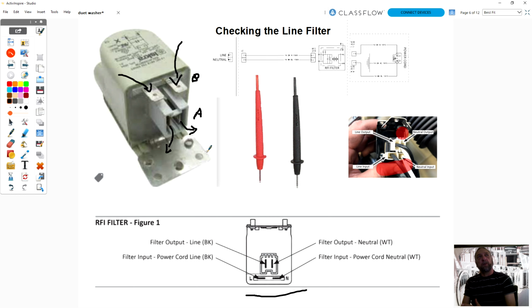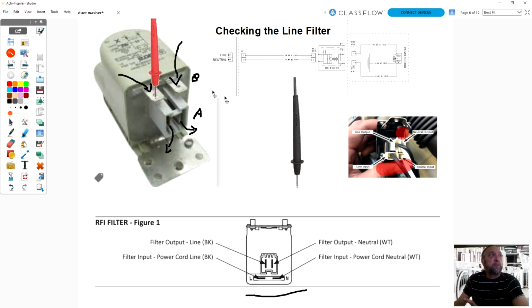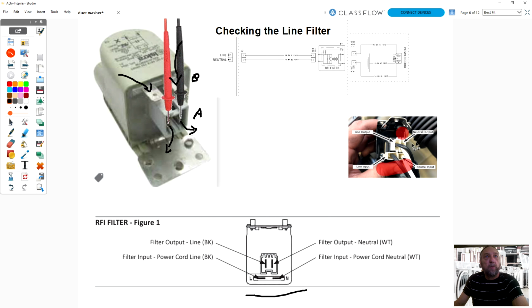A lot of people wonder why I'm making such a fuss about this. Many people look at that line filter and don't understand what's going on inside it, or how to test it. All you have to do to check if it's working properly is test B, which is power coming in. Put one meter lead here and here on the bottom, and see if you get 120. Then go over to the plug, the two terminals on top, and check for power out.